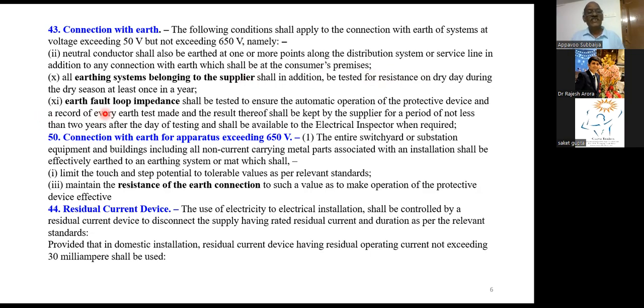And as far as the consumer premises is concerned, earth loop impedance, this is earth fault loop impedance, shall be tested to ensure automatic operation of the protective device. The earth fault loop impedance is the one that I have shown in our first slide. The protective earth conductor with the supplier, which is a source, a transformer or the generator, its source impedance, that is the winding, the line conductor impedance, then the protective earth conductor impedance. This will constitute not even 1 ohm. It will be mostly less than 1 ohm, depending upon the fault level and the distribution arrangement.